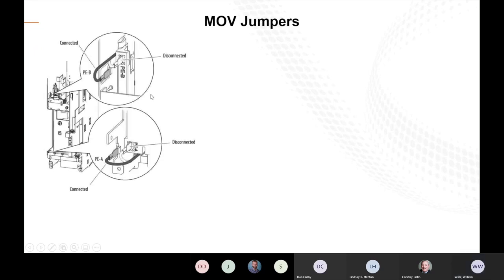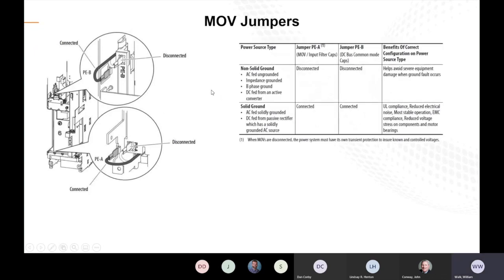So inside of the VFDs, we have MOV jumpers. You've got your PEA and your PEB jumpers. Now, you might ask yourself, what do I need to know this stuff for, or why do I have these inside of the VFD? So depending on the type of grounding situation that you have at your installation, if you have a non-solid ground or if you have a solidly grounded transformer, for your non-solid grounds, you're going to have these jumpers disconnected. If you have a solidly grounded configuration at your facility, then you're going to want to have these MOV jumpers installed on the VFD.